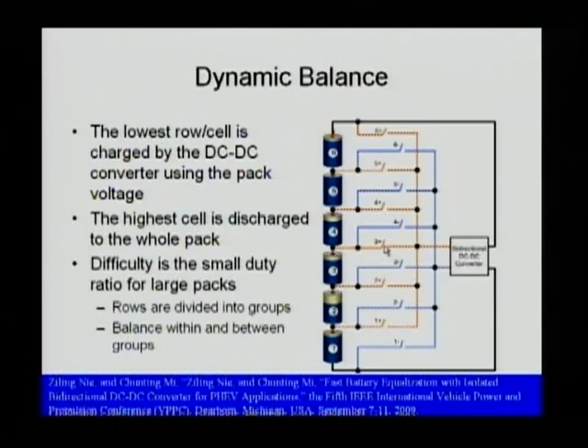This DC-DC converter tries to get energy from the string and then charge the lowest cells in the string. Once all the cells are charged to a similar voltage, it stops. Every time it identifies a lower cell, it charges that cell from the string. It's very effective, and because we have only one DC-DC converter in a large string, the size of the system can be relatively small for this balancing system.